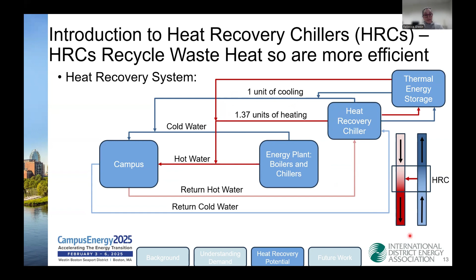So now you can use your heat recovery chiller when there's simultaneous heating and cooling happening on your campus. This is real data for Stanford, with the orange data here representing the heating demands for the campus over the years, and the blue data here representing the cooling demand. What you can see is that at the same period of time, there's both heating and cooling demand within the campus. Now, if we take advantage of a heat recovery chiller, all this purple area shown here can be met with the heat recovery chiller instead of traditional heaters and boilers.